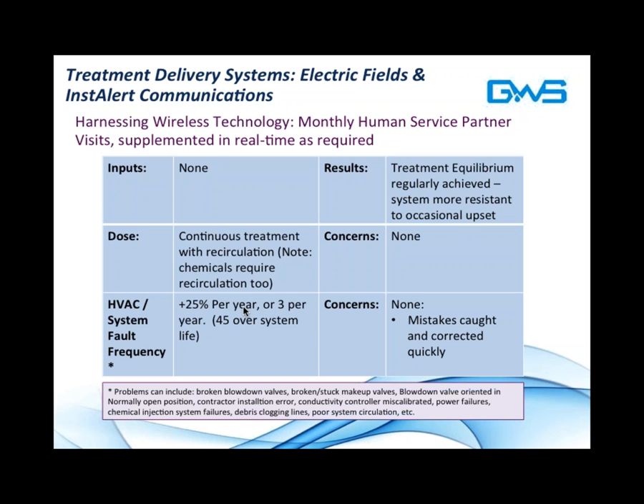No concerns there. But let's consider that there are system upsets, the same as with chemical inputs, at the rate specified by most chemical service partners, which is to say 25% of their jobs in a given service partner's visit will experience a system upset. Equated to a single job, that means each cooling tower will have 3 hiccups per year. And those problems can be read about in the asterisk down there, which include broken blowdown valves, stuck makeup valves, valves oriented in incorrect positions due to installation error, etc. When these system upsets occur, because of remote monitoring, they can be caught very quickly.